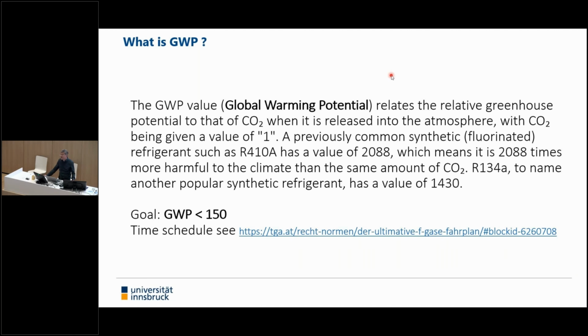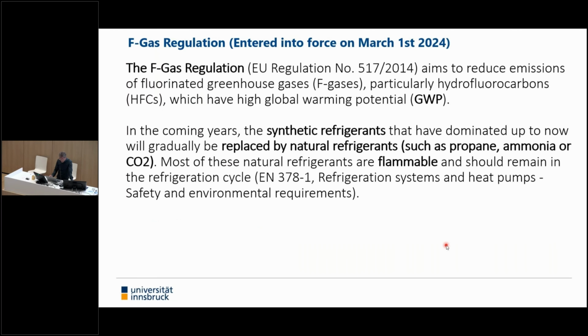And the goal is to bring them down to values lower than 150. If you are interested in the time schedule, you'll find the link where you can find the schedule for reduction of these GWPs of the refrigerants according to the legislation. The legislation is the F-gas regulation, which entered in force on March 1st, 2024.